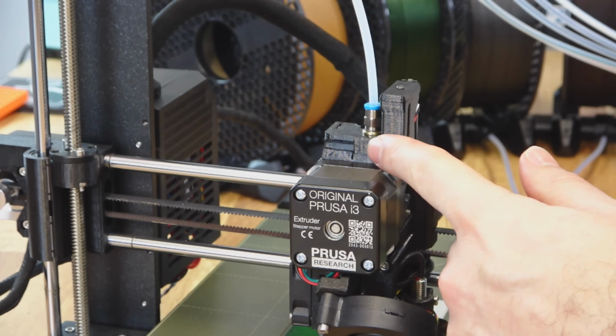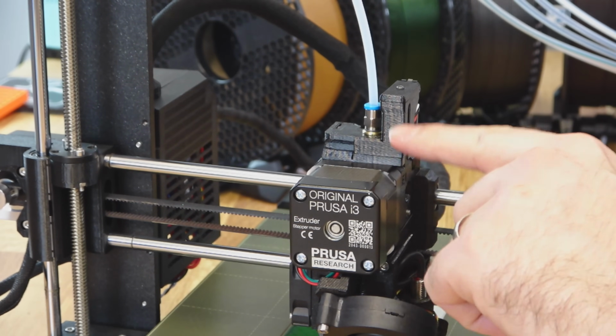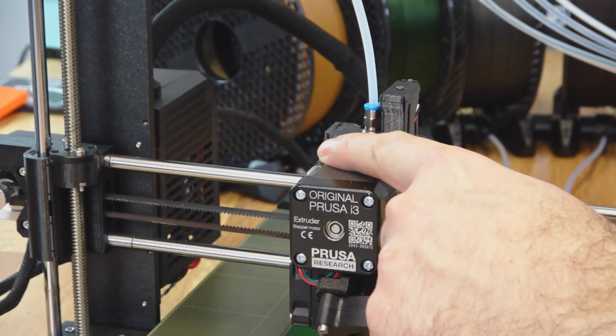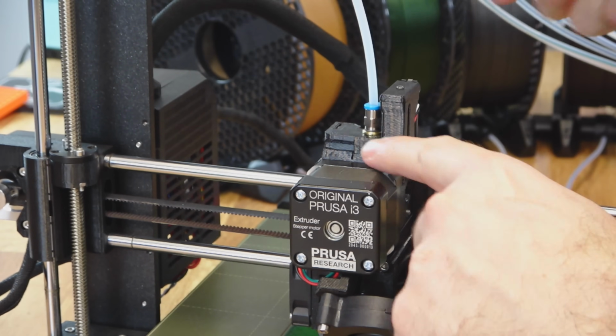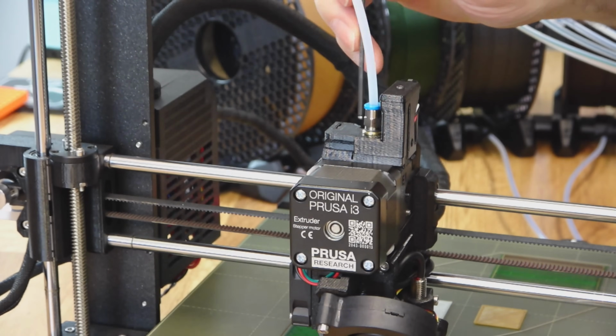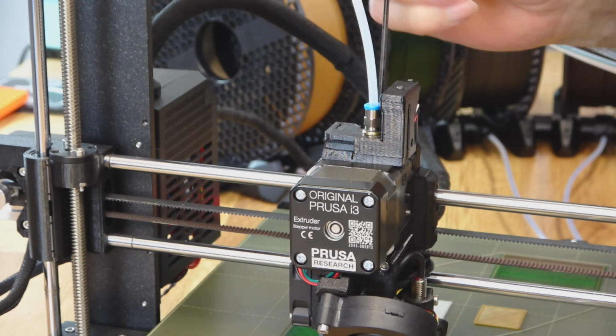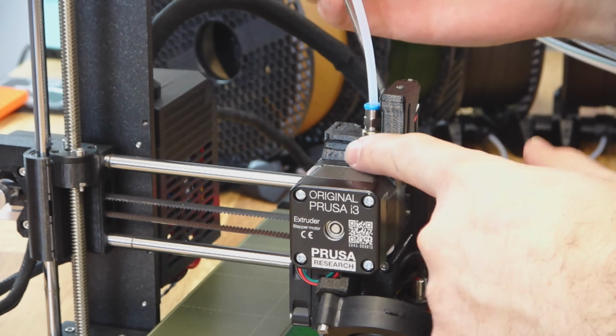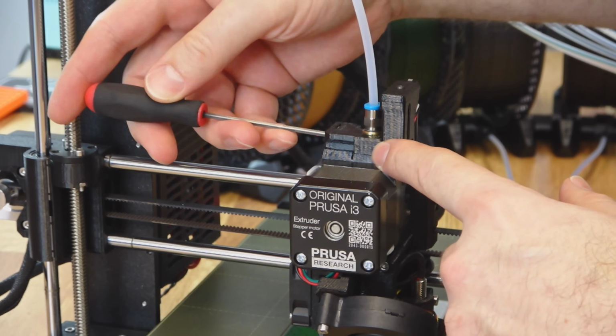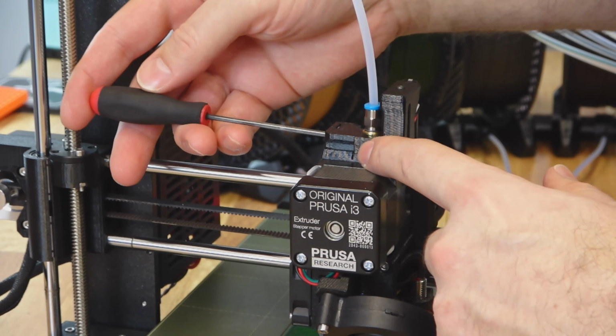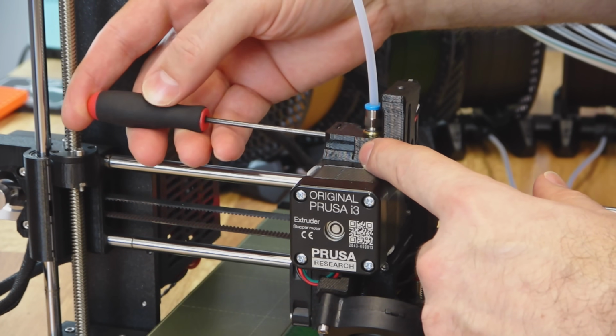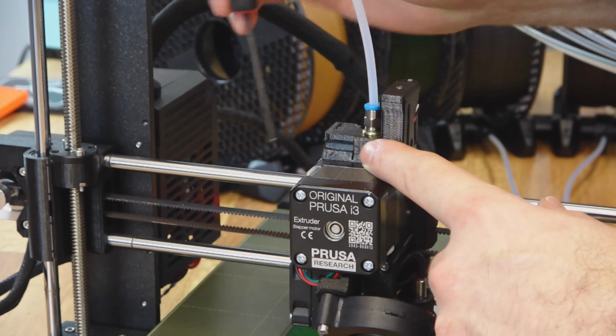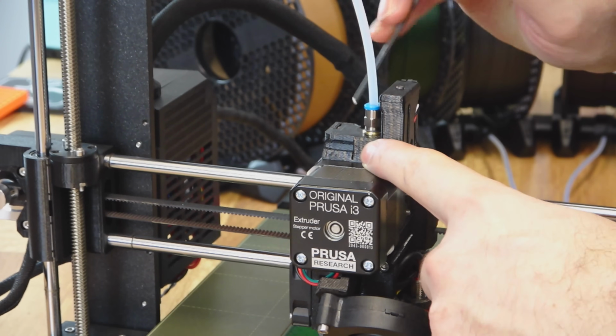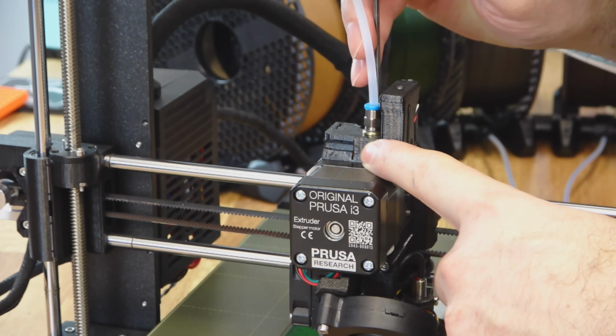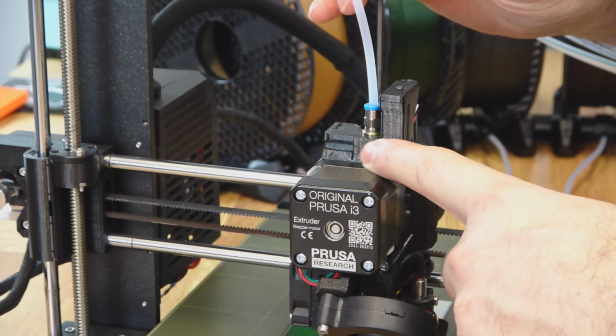So to decrease the sensitivity of the filament sensor, we need the chimney to move to the left. So you would tighten up the adjustment screw. The screw that holds it on, we're just going to back it out a turn so this part can move. And we're going to do a half turn on the adjustment screw, so make it a half turn tighter. That will reduce the sensitivity. We can lock our chimney back down.